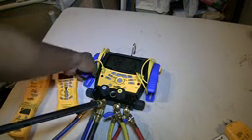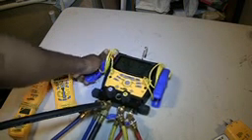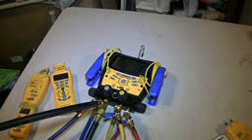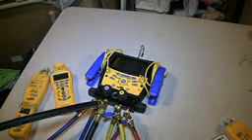The temp pros are pretty good, pretty decent. They pretty much clamp on most refrigerant lines. I haven't had any issues with these, but just be very careful because even though the manifold is pretty sturdy and solid, these clamps aren't. And I have broken a couple, and plus they're freaking expensive, which I don't understand why. But nonetheless, clamp pros are pretty good, and the length of the cable is pretty decent. So if you have a big or tall or wide outdoor condenser unit, or even an outdoor package unit, and you can't find a place to hang the manifold, at least they give you enough cord to get to the line set where you need it.